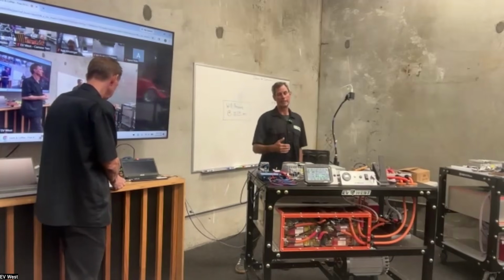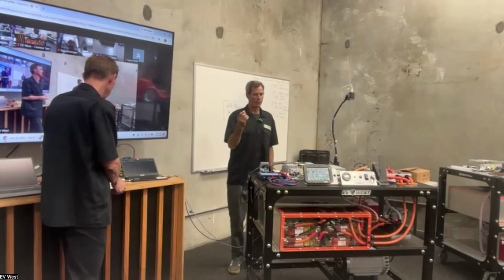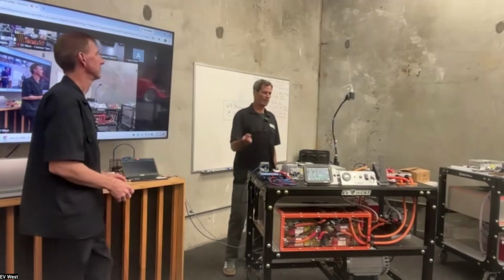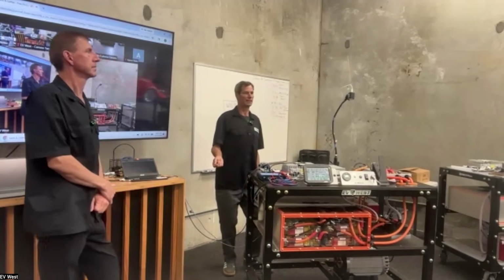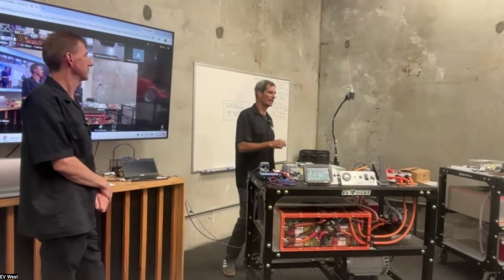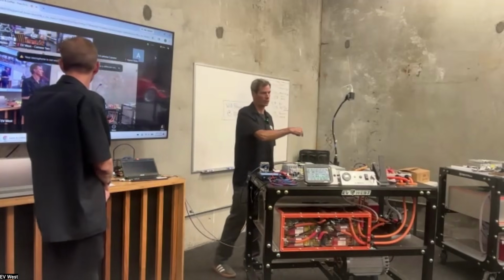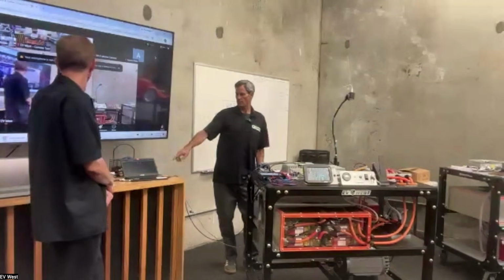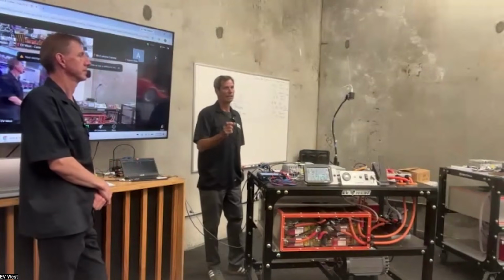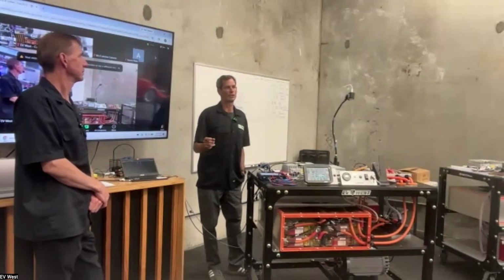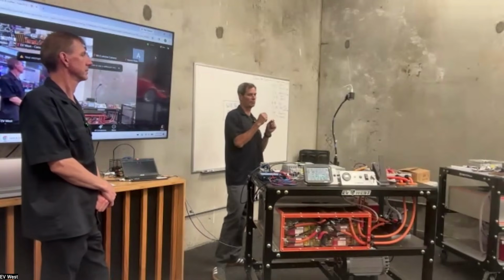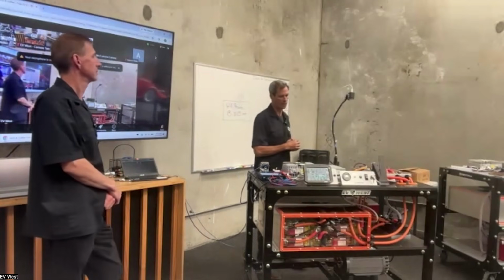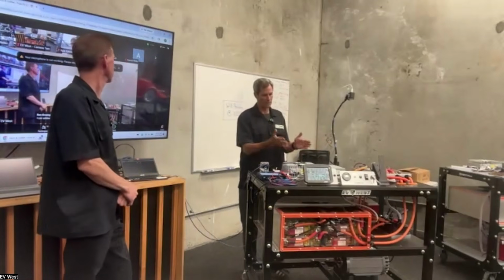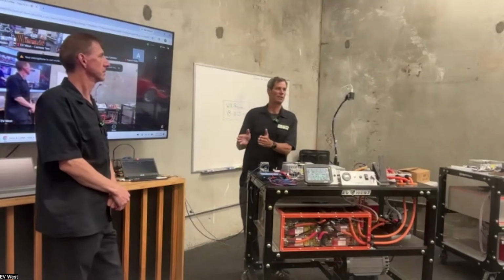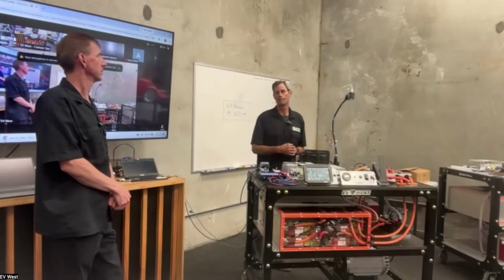The software is really neat too, because when it has a fault code, next to it the manufacturer has programmed in common causes automatically. So for that same fault code with the temperature sensor, the manual on the computer would say check your motor temperature sensor or your motor thermistor, and give guidelines for what a nice resistance reading is. So it not only does the diagnostic, but sets you on a suggested path for remedying the problem. Very good.